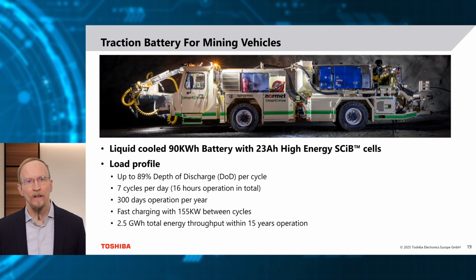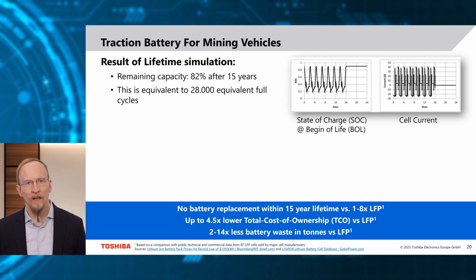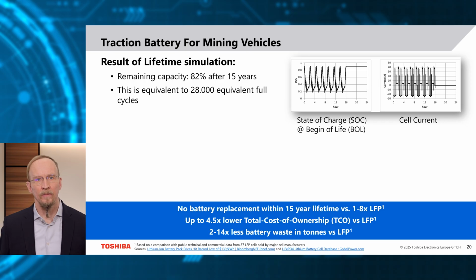Between each cycle, the battery will be recharged with 155 kilowatt. During 15 years of operation, the total energy throughput is still 2.5 gigawatt hours. The result of the lifetime simulation is that the remaining capacity after 15 years is still 82%. This is equivalent to 28,000 equivalent full cycles.